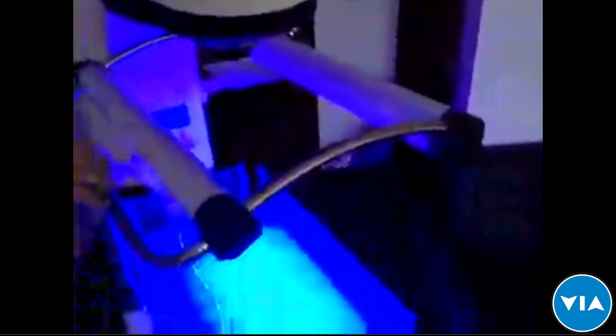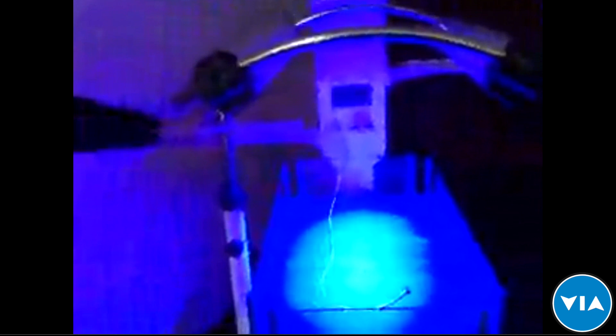Now, before I go to the Wallaby Warmer, I want to show you how nicely those two devices fit. We just roll them in together. And you can see, because we have that gap, there's no obstruction between the heat wave provided by the radiant warmer and the phototherapy itself. So it looks like this. It's a really, really cool solution for places that have to be careful with space. And we don't lose any of the coverage of the patient because we don't have to tilt the overhead unit or put it on the side, or any of those things.